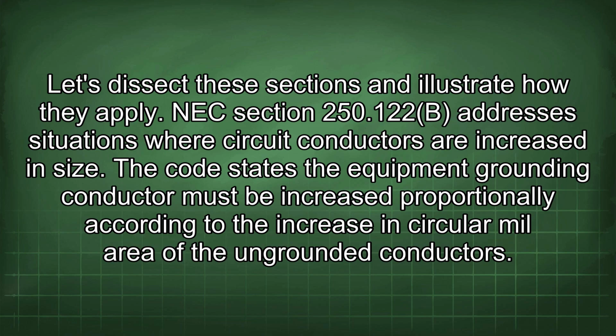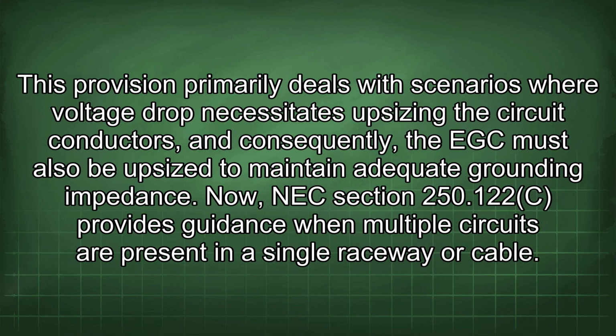NEC Section 250.122(B) addresses situations where circuit conductors are increased in size. The code states the equipment grounding conductor must be increased proportionally according to the increase in circular mil area of the ungrounded conductors. This provision primarily deals with scenarios where voltage drop necessitates upsizing the circuit conductors, and consequently, the EGC must also be upsized to maintain adequate grounding impedance.